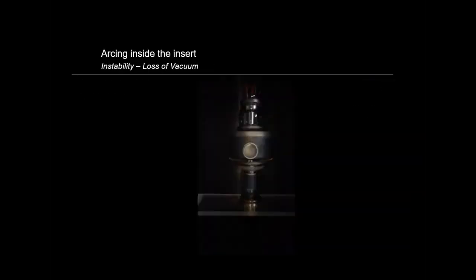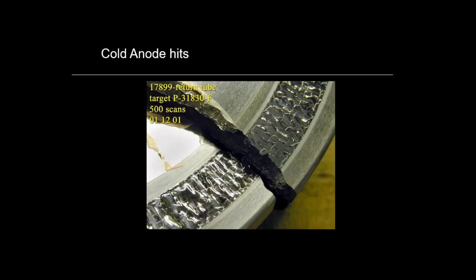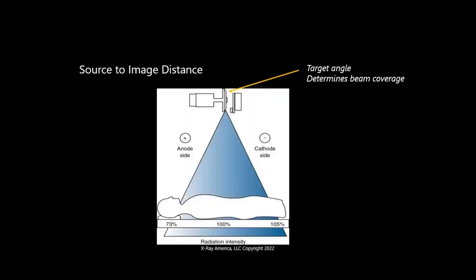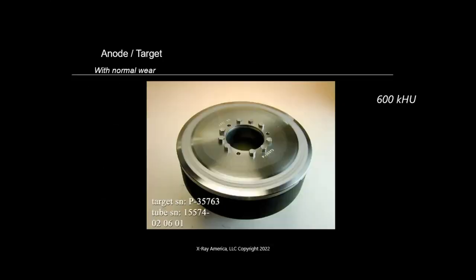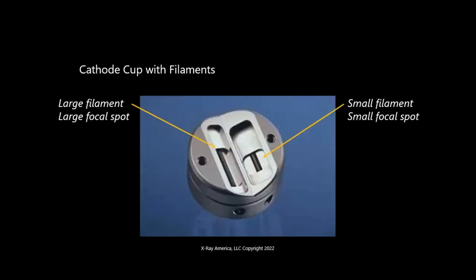So this is the cathode head. You look at one going around. You have a large filament and a small filament. The large filament is what bleeds off the electrons and creates the large focus spots. The small filament is what creates the small focus spots. Everything I'm talking about are parameters of the tube when you're buying an X-ray tube, where a system manufacturer is putting together systems, they need to understand.